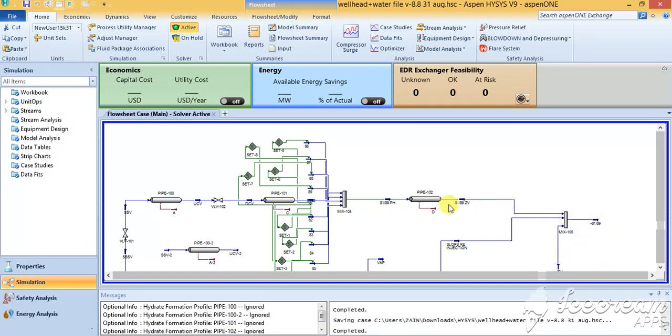mainstream. As you can see, here is a name known as the ZV, that is the emergency shutdown valve, that is upstream of the pipeline. This is basically your emergency isolation valve. This emergency isolation valve acts through the ESD system, so that if you are having an overpressure case scenario, this ZV will activate itself, it will turn off and it will not allow the fluid to pass through this.